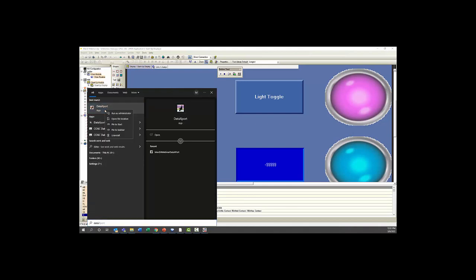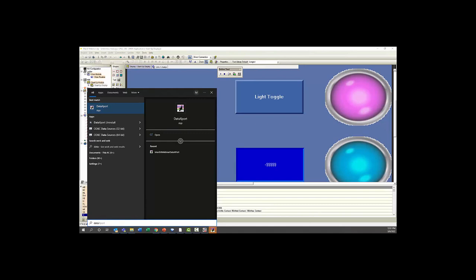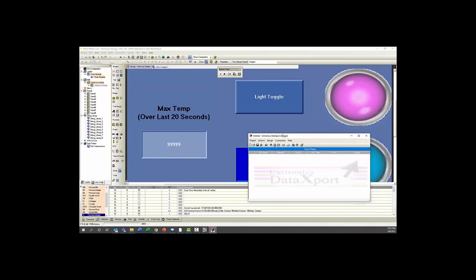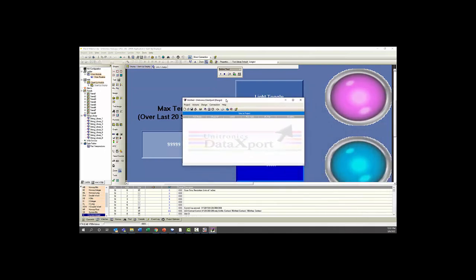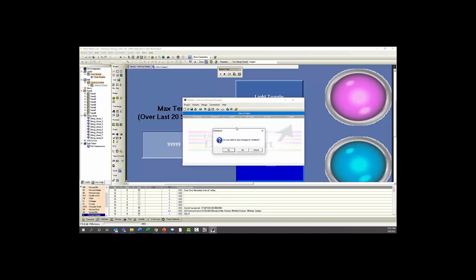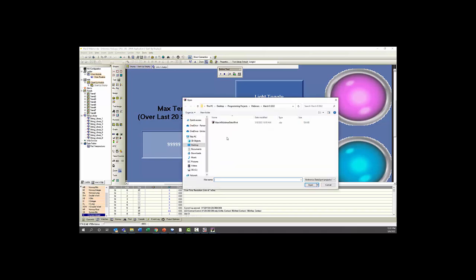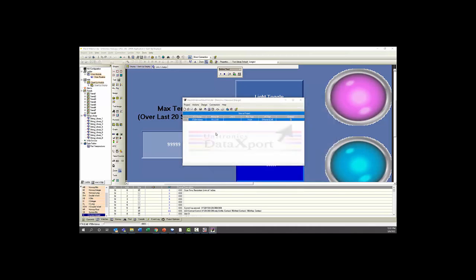Just like any other software that we offer, you're going to want to make sure to run this as administrator. If you don't run it as administrator, you're likely going to get some sort of runtime error or other sort of error. So here, since I've already created a project, I'm going to open a project, and what you have here is we have a PLC that's been added. You'll see the PLC name matches the name we set up in the ladder. The IP address matches. I don't have any unit ID set up for this unit. The PLC type will show here, and the PC port you're connecting to. It gives you the option to enable or disable this PLC so that when you run the project, you only connect to the PLCs that you want to connect to and pull data from.